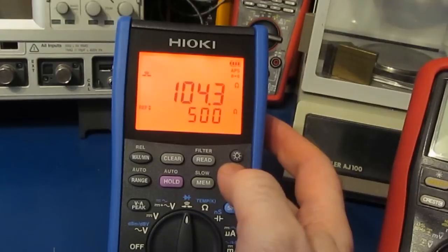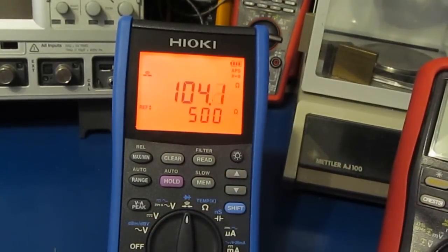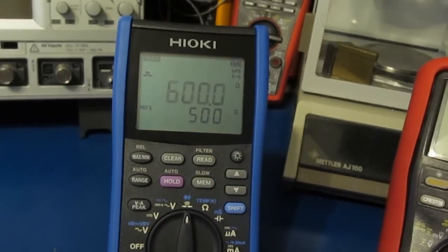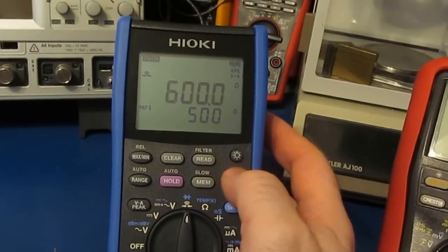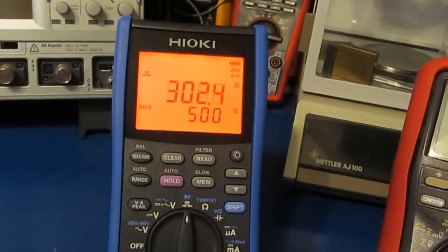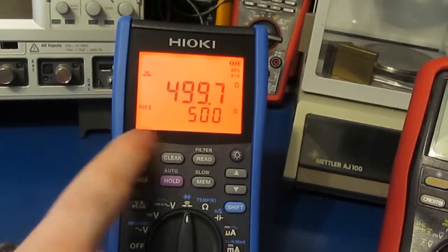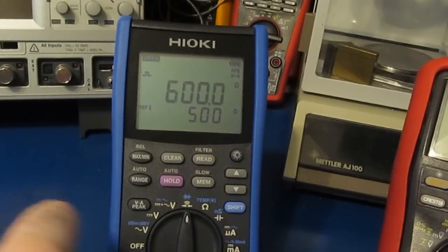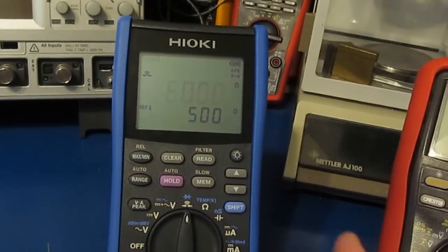So let's increase this to 500 ohms - you can see it's reading that just fine. And let's increase our resistance - so there's 600 ohms, you can see it's no longer picking it up. Looks like that's the upper limit of it. So yeah, we're right on the cusp right there, it flips right at 500 ohms. So that's a nice feature on this meter, that you can program that threshold point, which I could never do with the Brymen.